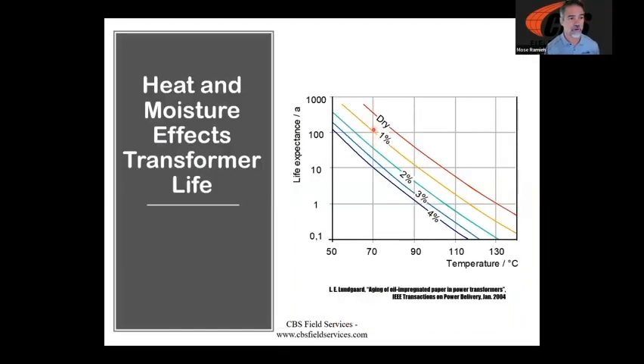The cooler we can run our transformers, the longer they're going to last. I'll just use this as a quick example. If we have a 1% dry transformer operating at 70 degrees C, that transformer's life expectancy, based on the paper I note below, is about 100 years. Well, just a simple increase of 20 degrees C, same 1% dryness, operating at 90 degrees C, shortens that lifespan down to almost 10 years. So a significant decrease with just a 20 degrees C temperature rise.